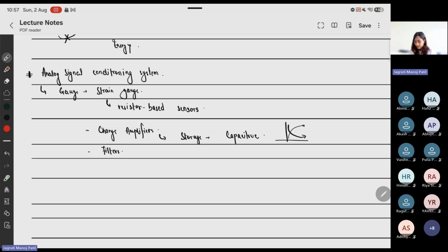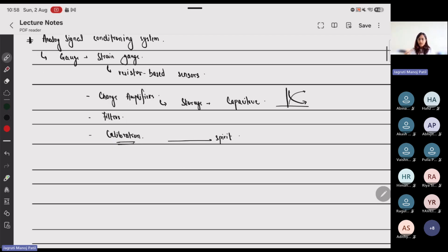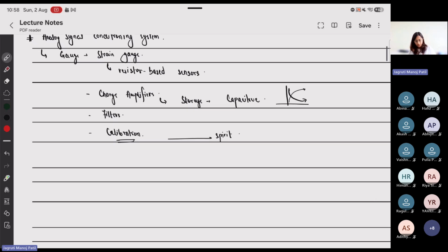that we talked about previously, but I guess this session does not have those. And then for calibration, to work on a physiological signal, your system should always be calibrated to a reference spirit level, to ambient pressure, to temperature, so that only then can you reference that particular value to the actual human's measurement that you're trying to do.